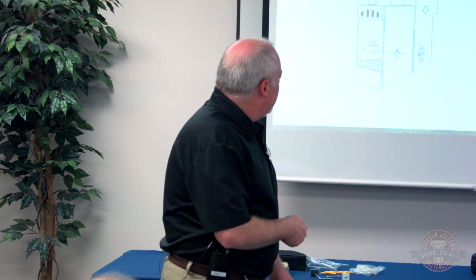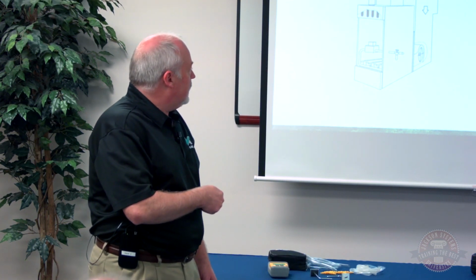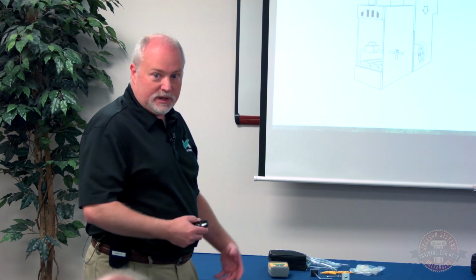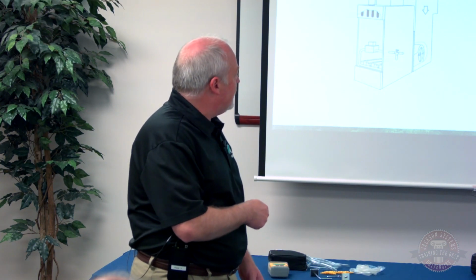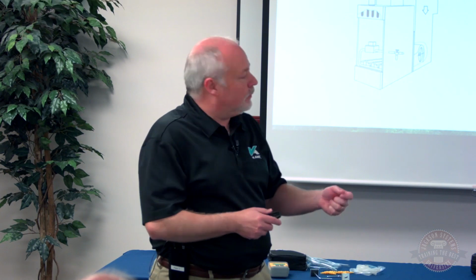The other thing that we can do with our manometer is we can measure draft. Okay. So typically that draft is taken in our flue pipe. One thing to remember, equipment that's rated as category 1, so that would be equipment that vents with B vent material, is going to have a negative pressure in the vent system, even if it's got a draft inducer. A lot of techs may see that draft inducer and say, hey, I got a fan that's blowing that exhaust out. It's not really blowing the exhaust out, it's fan assisting the draft through the appliance. So if you've got a piece of equipment that's vented with B vent, when you check the draft, it still should be negative pressure. Okay?